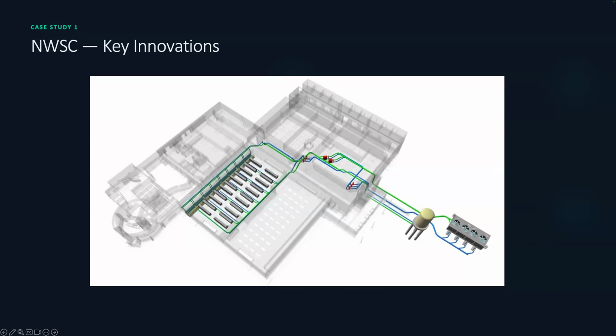Was this on purpose to test the system, or was this just an event? No, it was a control sequence. Oops, when we were doing an upgrade. Typical kind of thing, right? It went to a system default, and the system default was normally closed, and it should have been normally open. The fun way to find the bugs in the system. Yes.